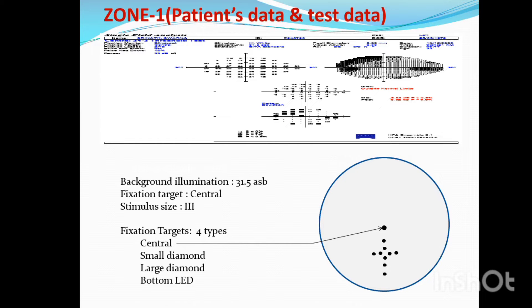Basically, the Humphrey machine will be able to test the patient with visual field defect. We are able to test the patient with visual field in a semi-dark room. The patient has been occluded. The Humphrey presents lights in the middle of the visual field for the patient.